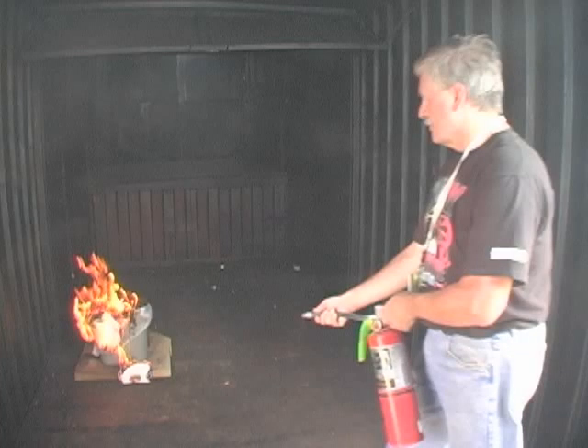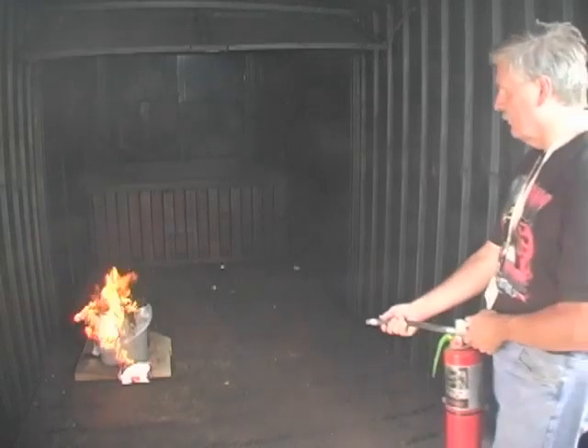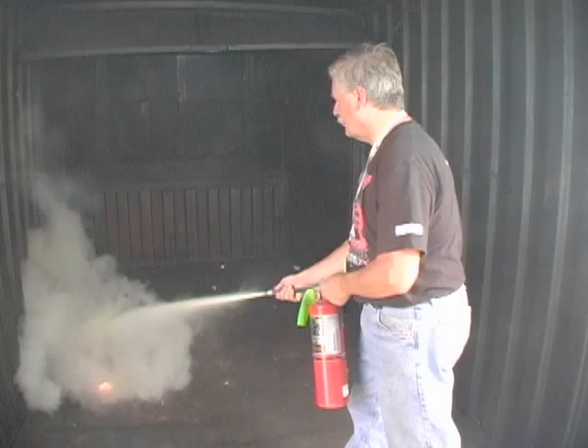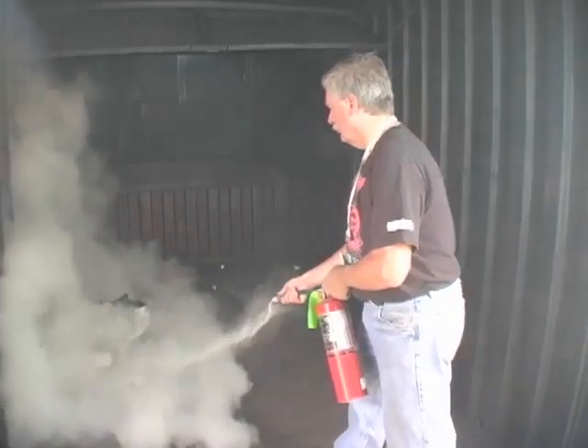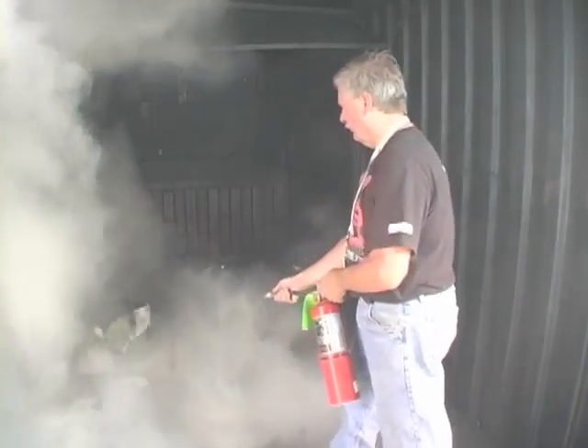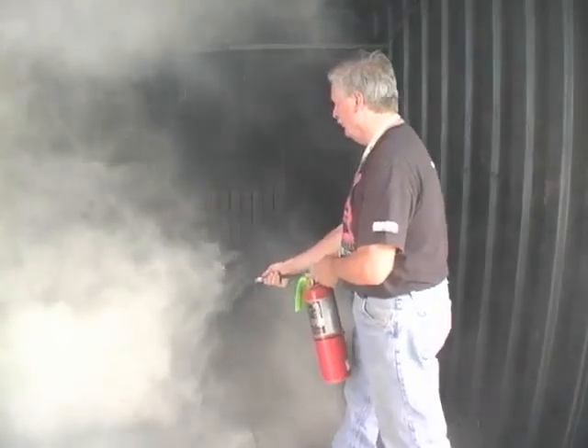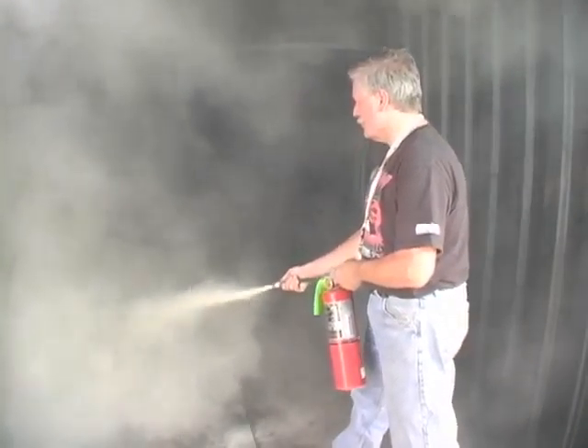A stands for aim. Aim the nozzle at the base of the fire, between the fuel source and the flame. S is squeeze. Squeeze the handle to discharge the fire-suppressing agent onto the base of the fire. The final S stands for sweep. Sweep the nozzle back and forth to extinguish the fire. Continue to sweep until the fire is extinguished or the canister is empty.